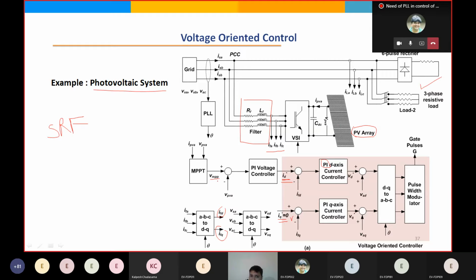So I'll compare the actual voltage with this MPP voltage, the maximum voltage corresponding to the maximum power point. I'll get an error which I'll process with a PI controller, and this gives the current. If I maintain this much current drawn from the PV array, then these two voltages will be matching.